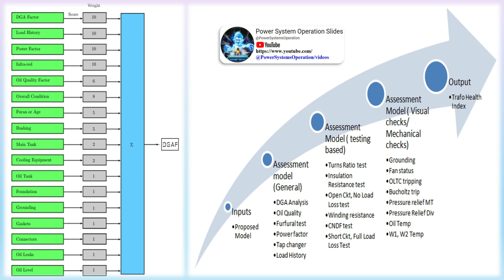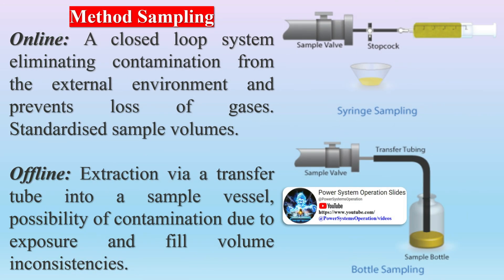Method sampling — online: a closed-loop system eliminating contamination from the external environment and prevents loss of gases, with standardized sample volumes. Offline: extraction via a transfer tube into a sample vessel, with possibility of contamination due to exposure and fill volume inconsistencies.